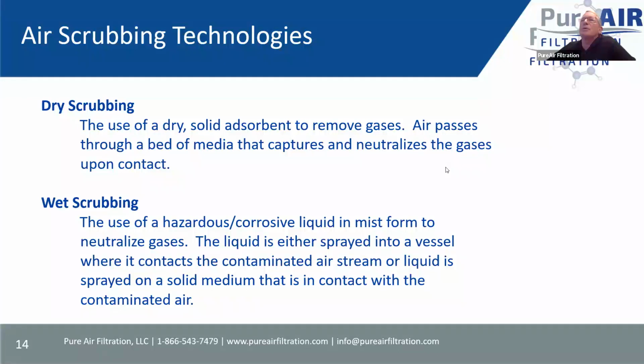Again, dry scrubber, which is the use of a solid adsorbent to remove the gases. The air passes through a bed of media that captures and neutralizes the gases upon contact. And then another technology in this industry is a wet scrubber. The wet scrubber is the use of a hazardous corrosive liquid that is either sprayed into the vessel where it contacts the contaminated airstream, or liquid is sprayed on solid media. So they'll have basically media that gets sprayed. But again, you use a caustic solution to neutralize the toxic gas.